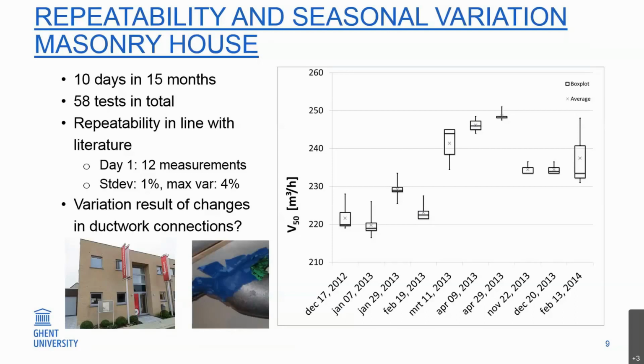One possible thesis could be that a different thermal dilatation of the masonry construction and the plasterwork ensuring the airtightness leads to larger cracks in summers at corners or joints. But this is only a thesis. We're not sure. It should be checked in laboratory conditions maybe. But a more straightforward explanation is that these differences are more random and a result of the changes of the ductwork connections, which are dismantled a lot during the tests.